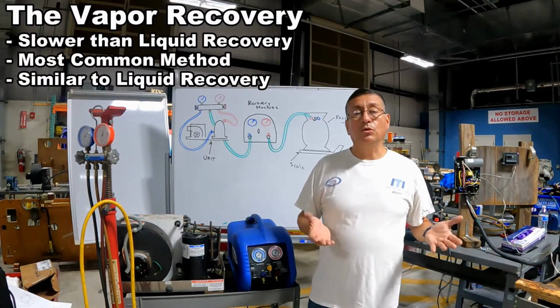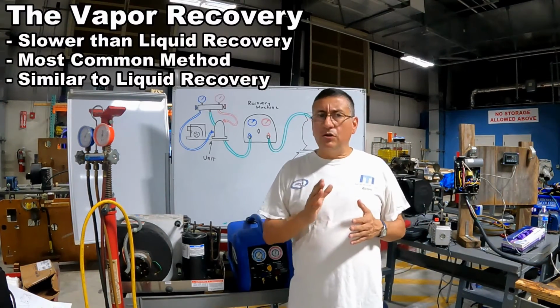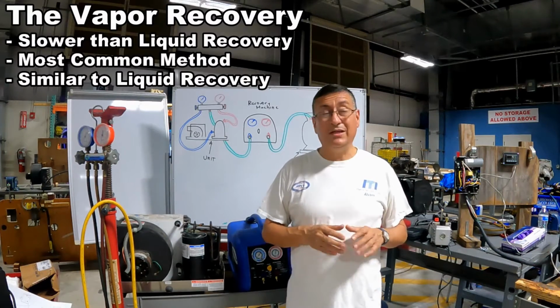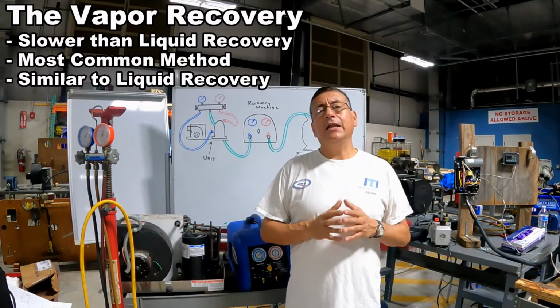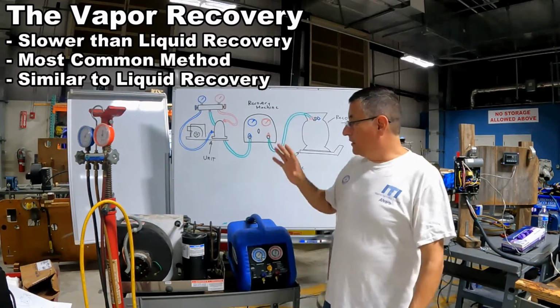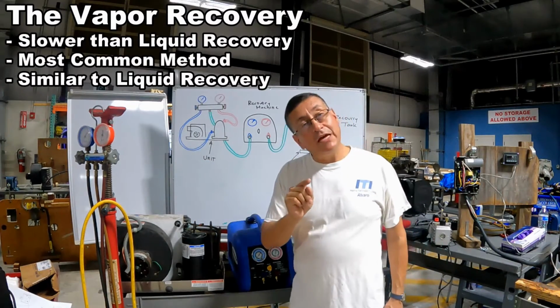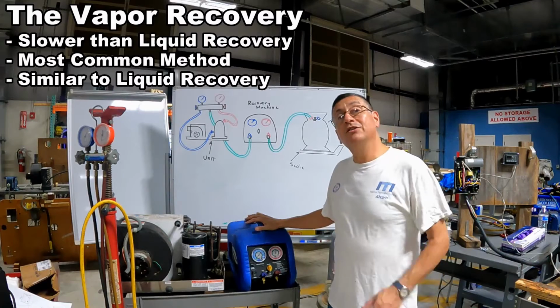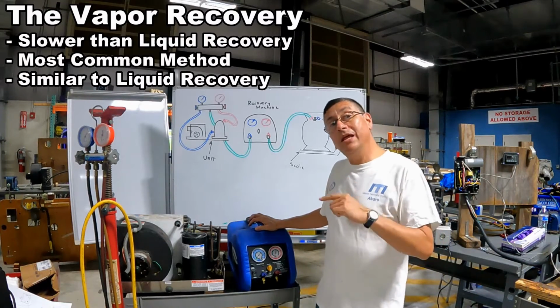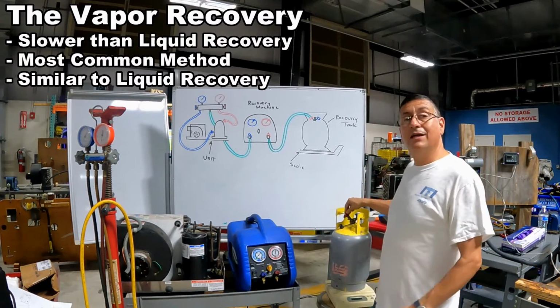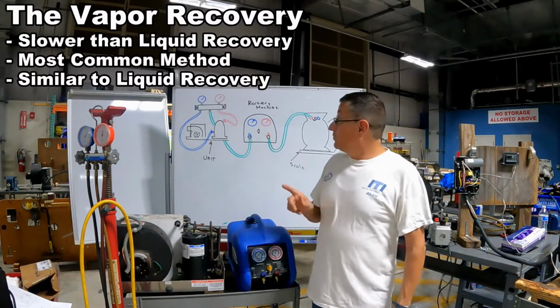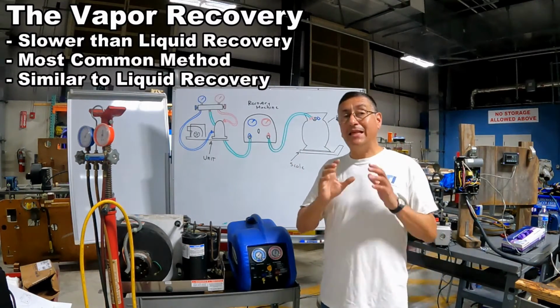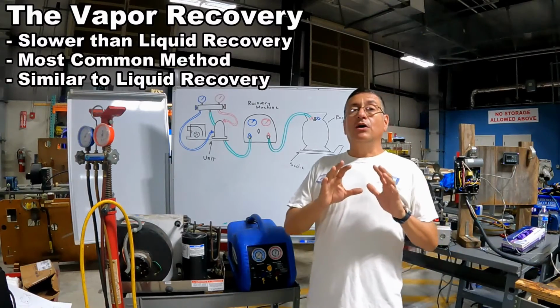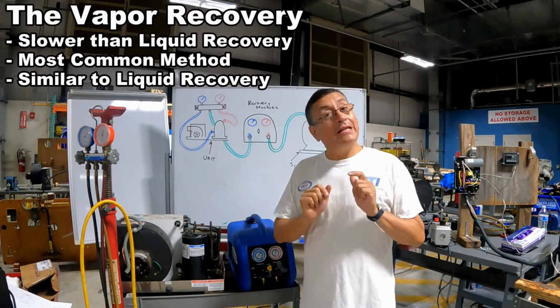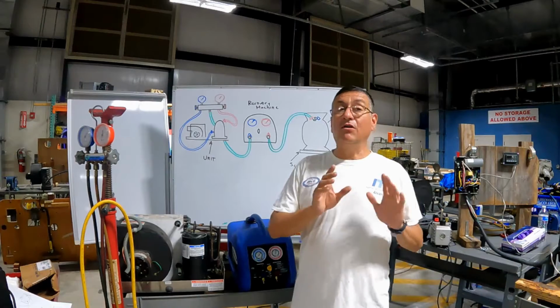The next method is the vapor method. The vapor method is a little slower than the liquid. It is the most common method used, and in this method the refrigerant is recovered in vapor state, and this equipment condenses the refrigerant into liquid, and after that it enters the cylinder in liquid state. We are going to use this diagram in order to recover the refrigerant, doesn't matter if the method is liquid or vapor.